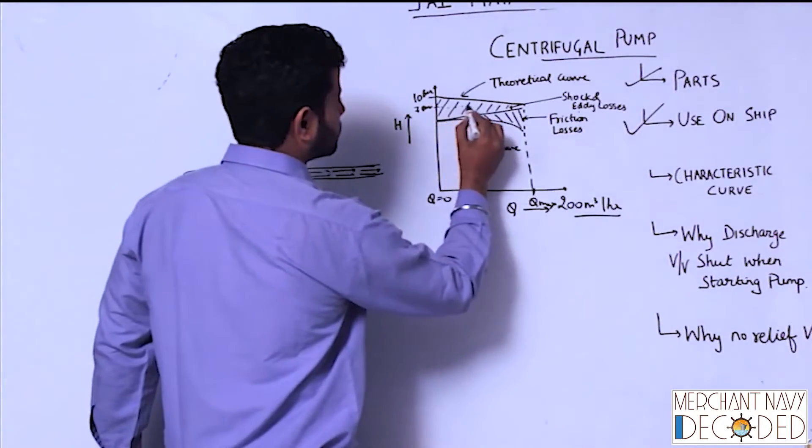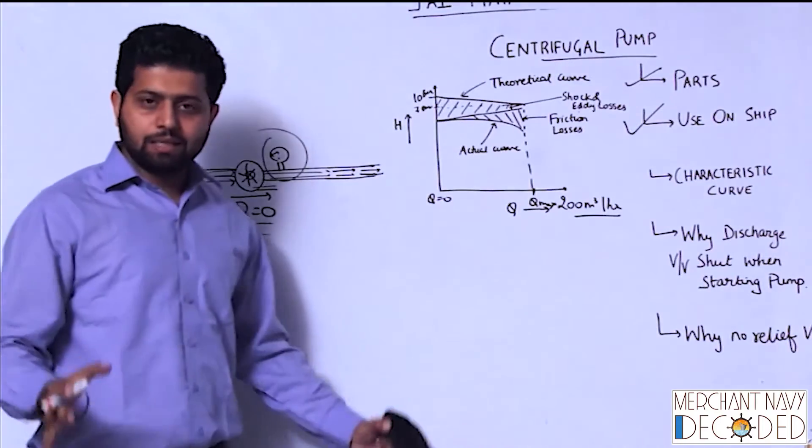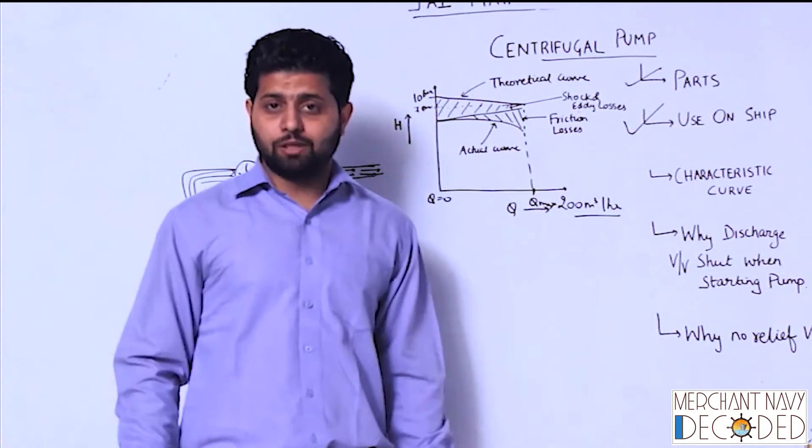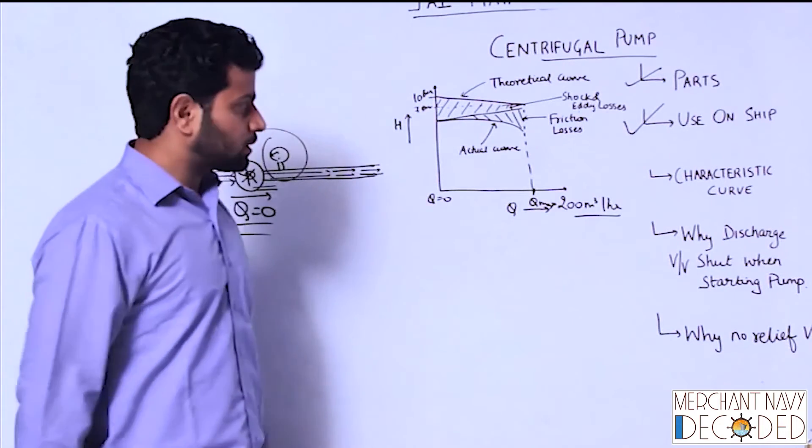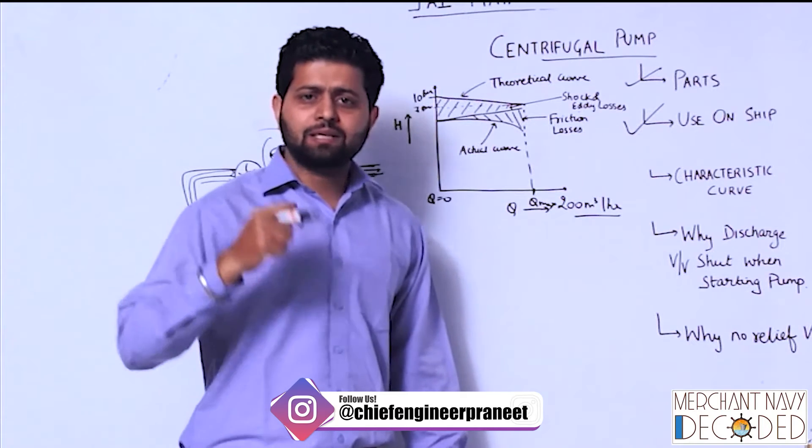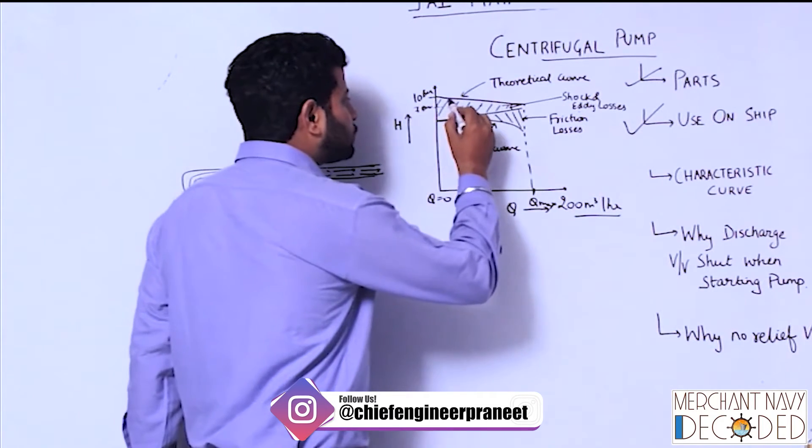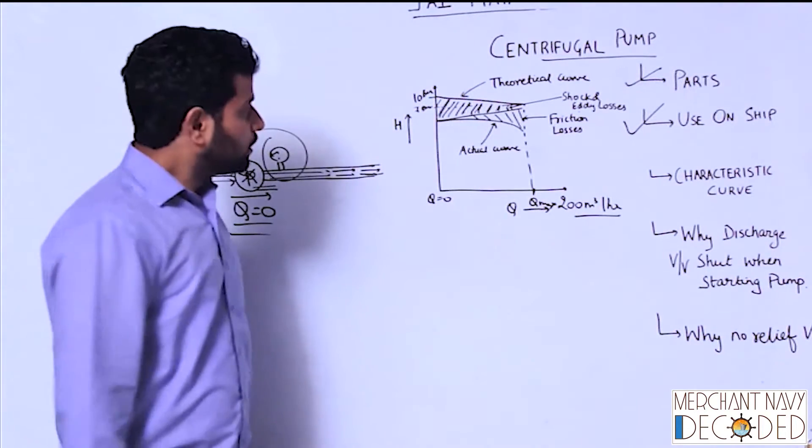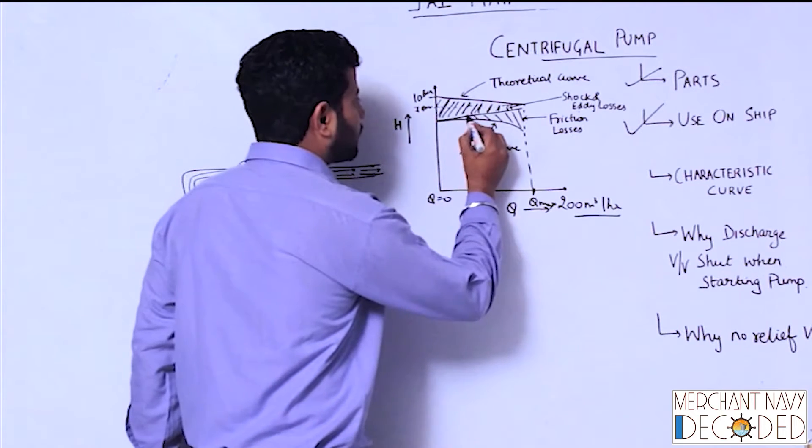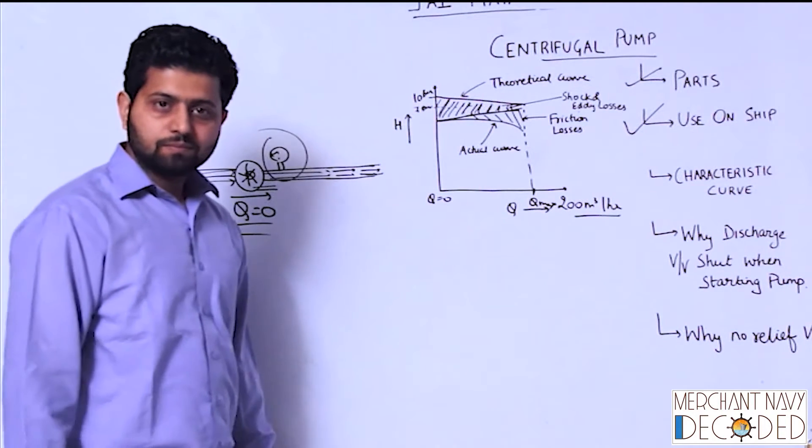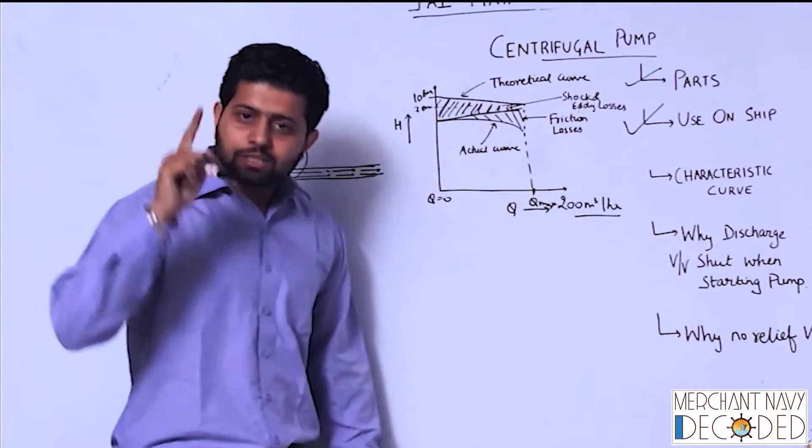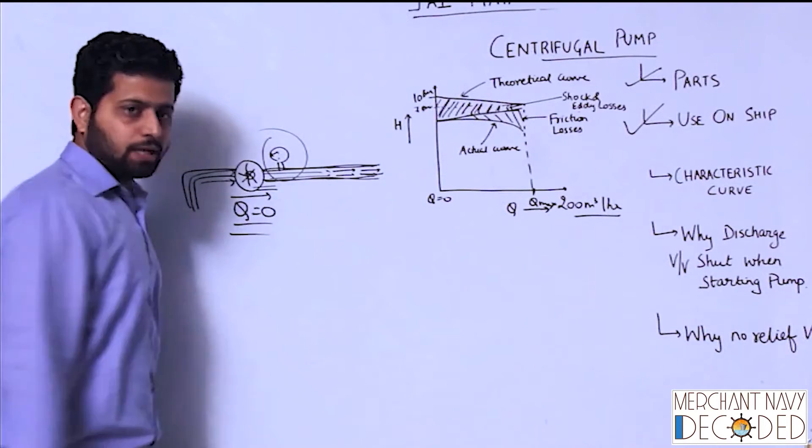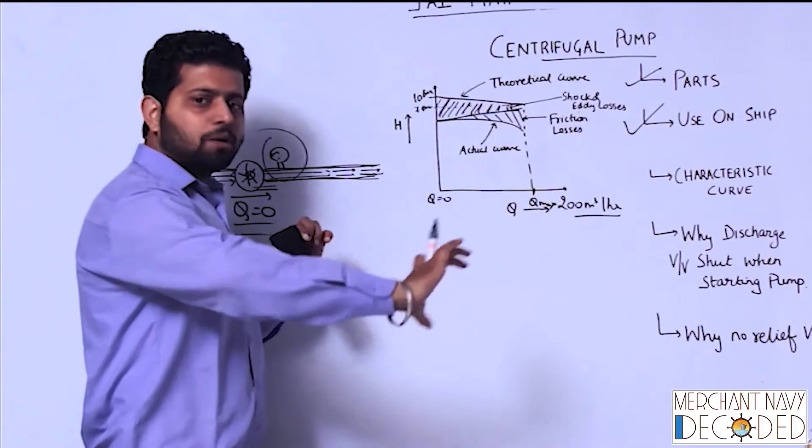I am talking about this curve now, the theoretical curve, but again this theoretical curve where I have not assumed any kind of other issues. But the first issue that comes is because of the impeller blade thickness and other mechanical conditions. There are some shock losses and eddy losses, due to which this curve now comes like this. But again it does not stop there.